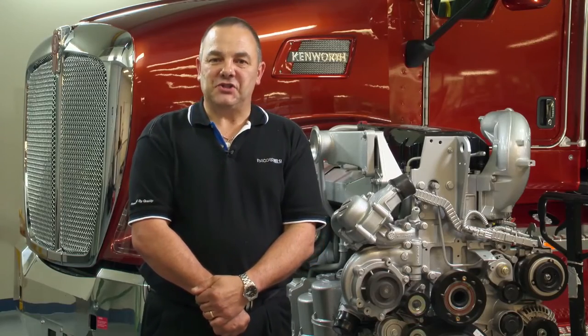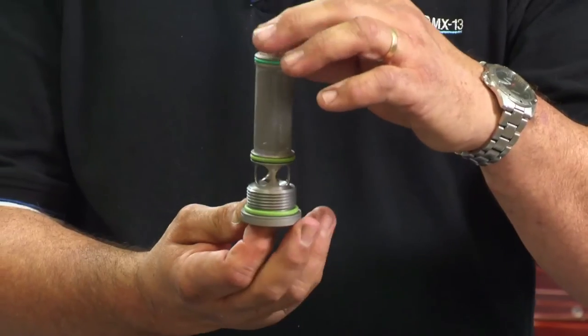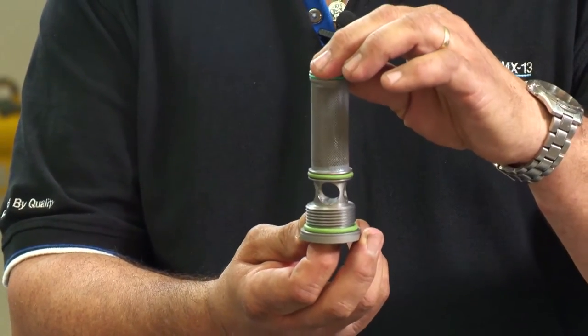The cooling system is protected by a strainer which is located beside the coolant pump. This strainer filters out any impurities in the cooling system. The coolant and strainer are serviced on a four yearly interval, where the coolant is changed and the strainer is removed and cleaned.